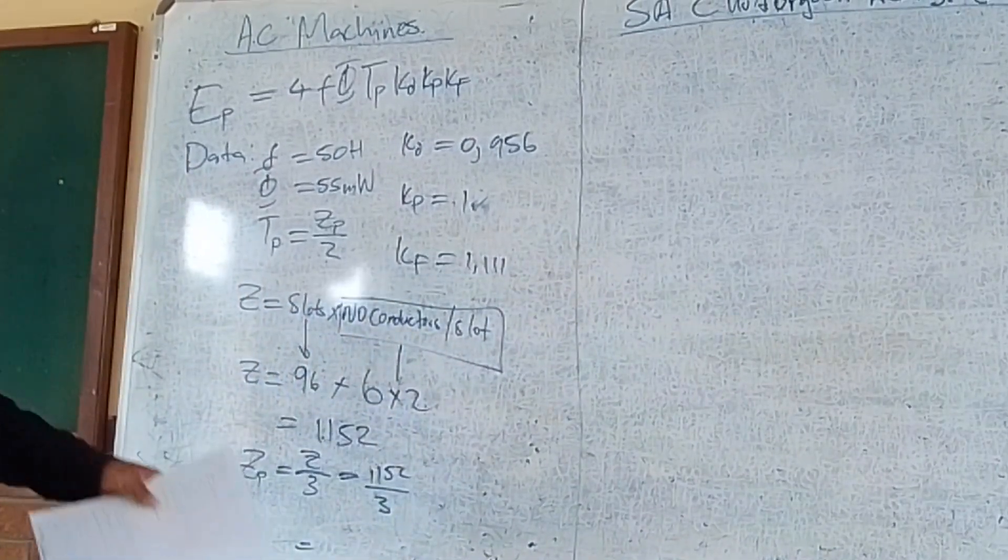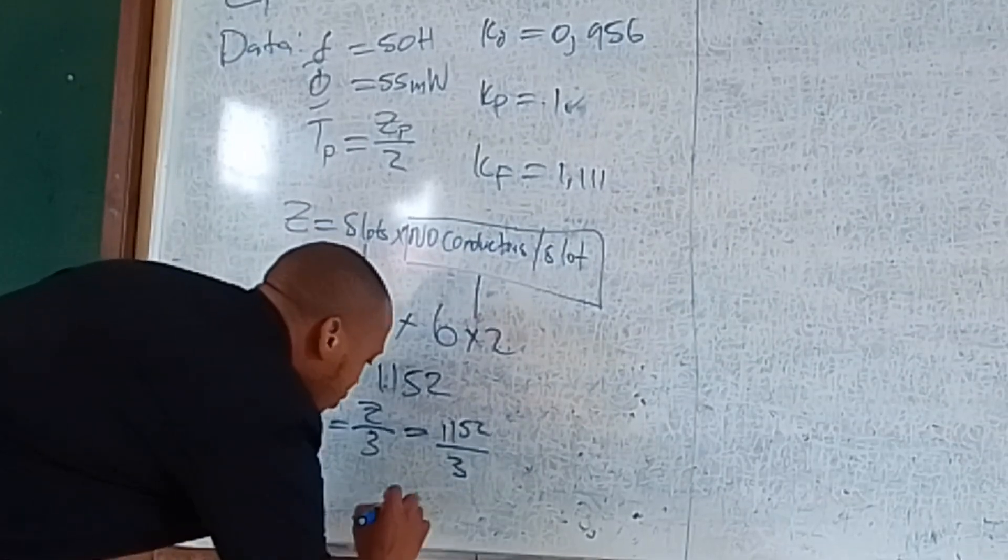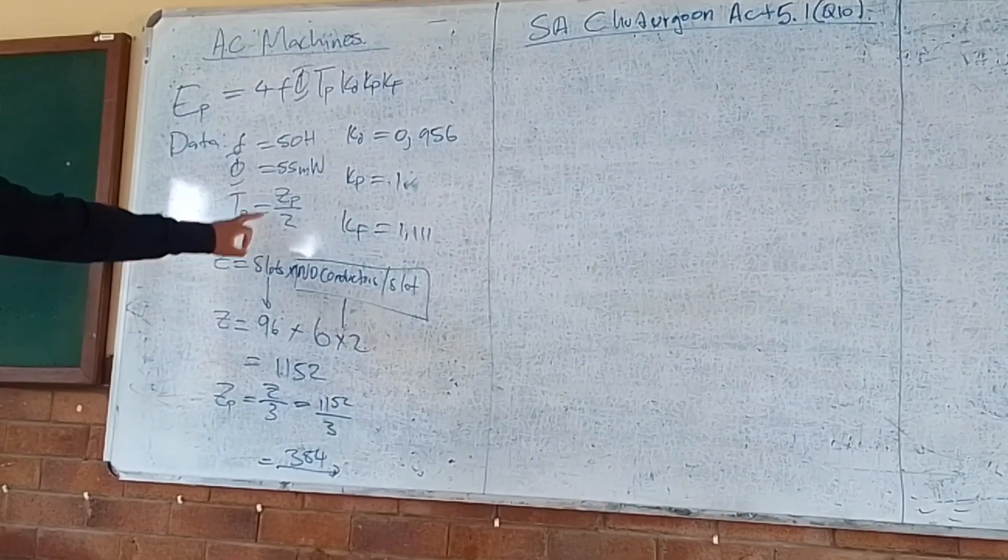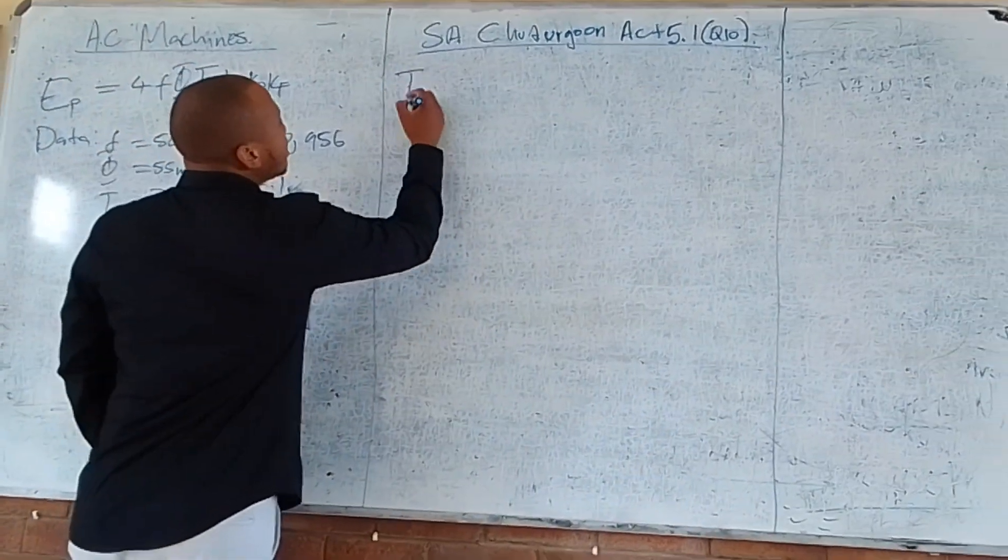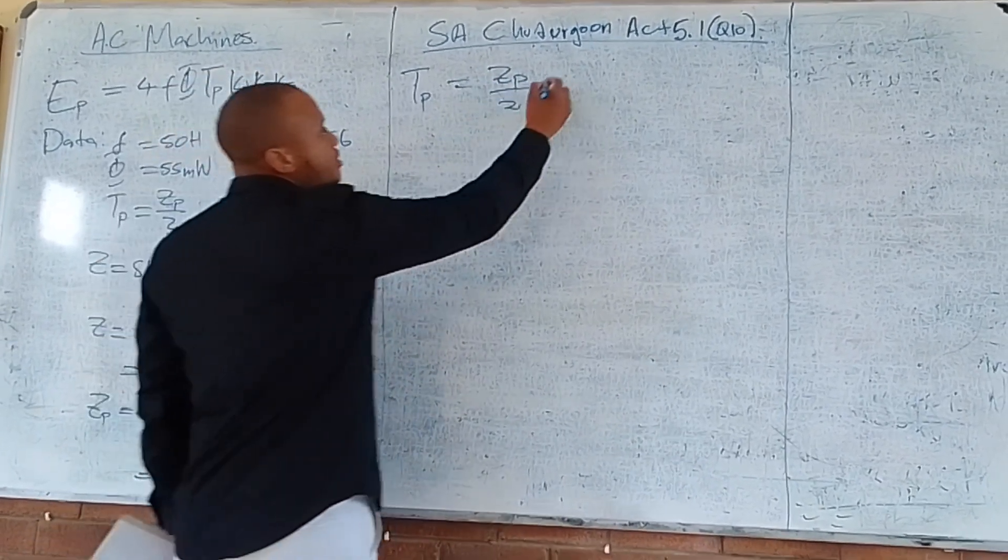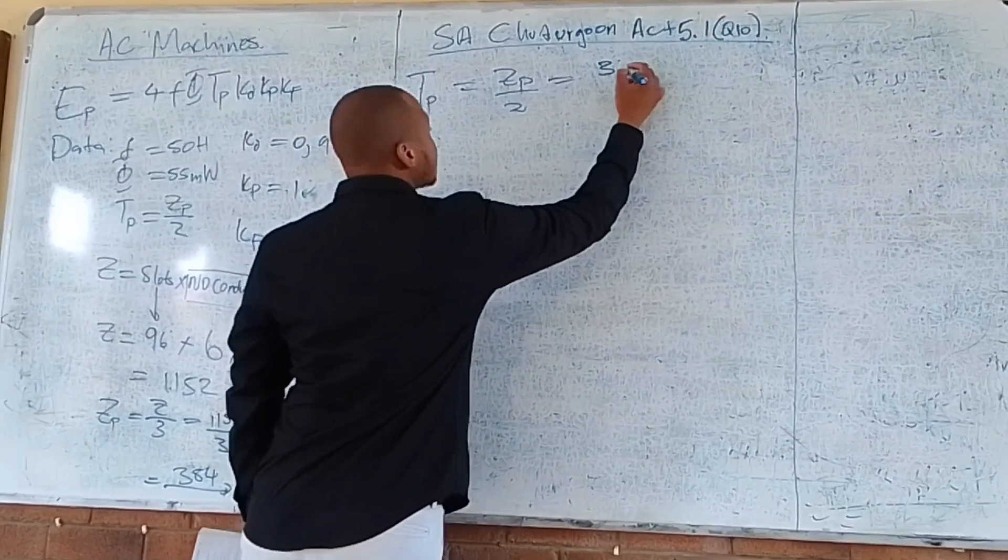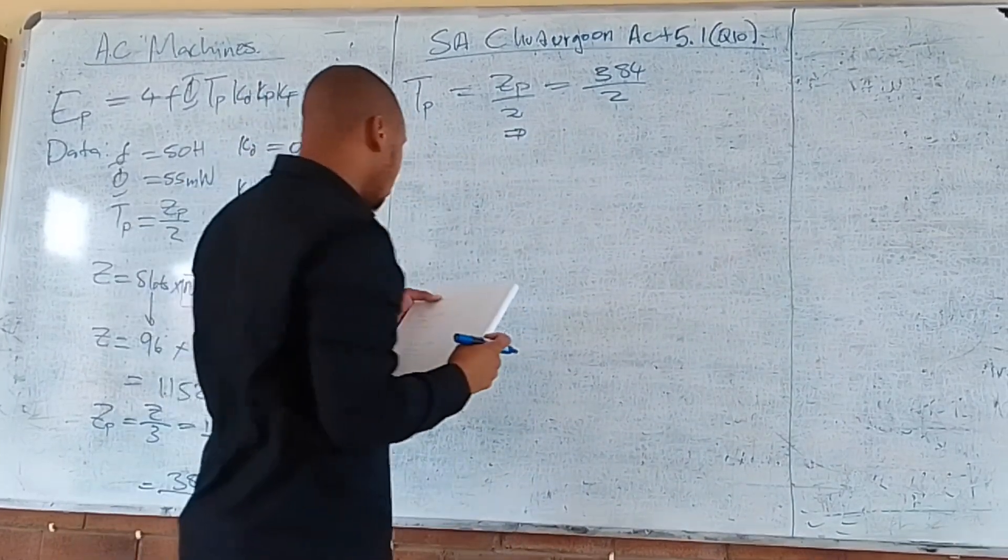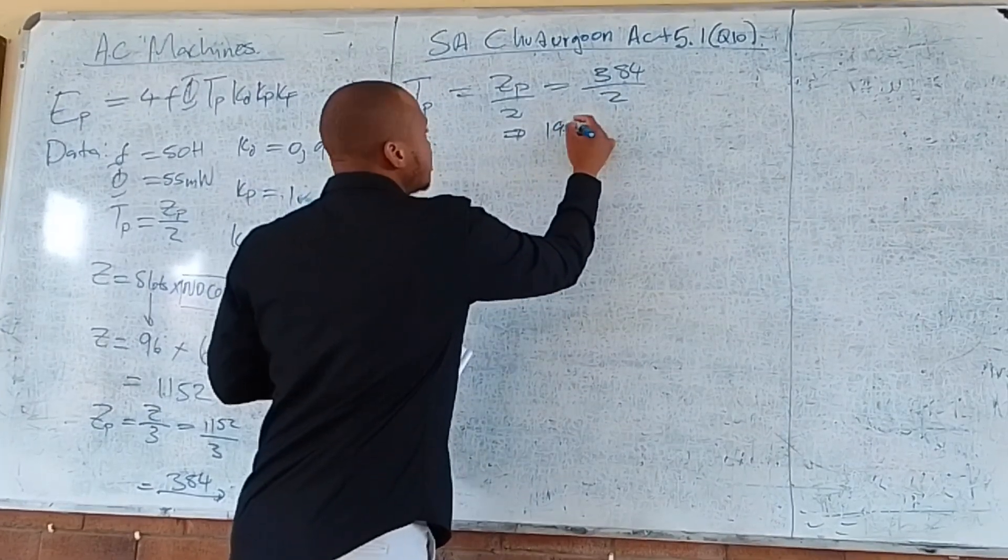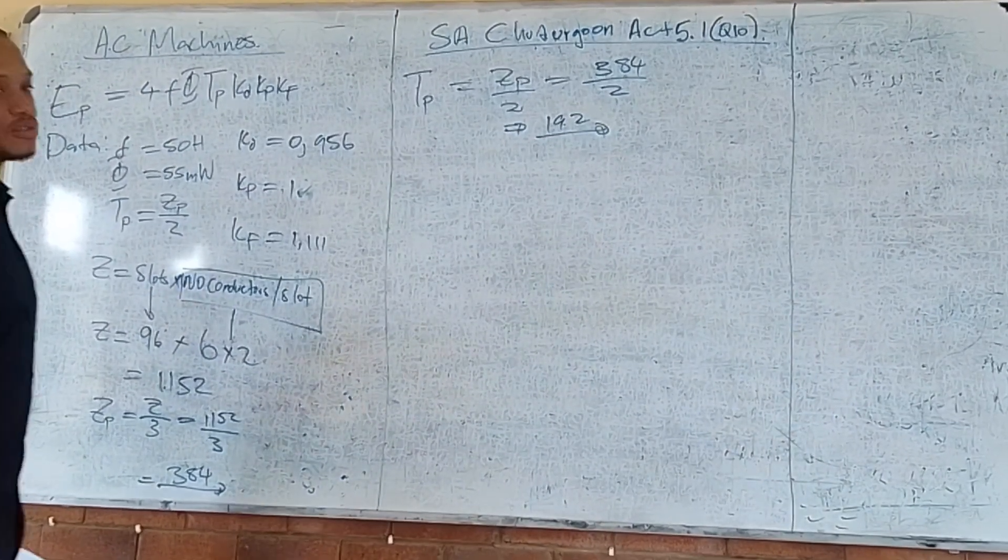If you calculate that in the calculator, Zp equals 384. Now we need to calculate turns per phase, which is Zp divided by 2. Tp equals 384 divided by 2, and that gives you 192. No units, it's just the number of turns per phase: 192 for this question.